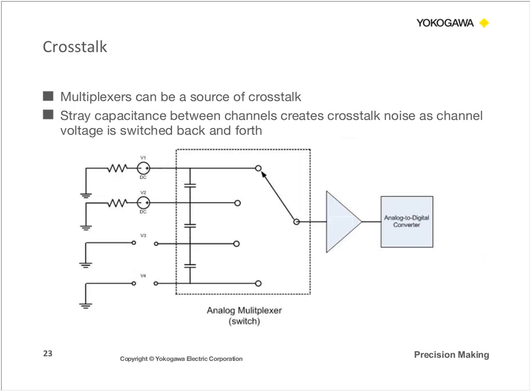So crosstalk is another issue that can occur because you have a ground loop. Crosstalk occurs when you have noise from one channel. Let's say you have a multi-channel data acquisition system. You have noise from one channel that carries over to the next channel. So we're defining crosstalk as the interaction between readings on two or more channels. And this is a pretty common occurrence for data acquisition systems today that implement multiplexing technology, where channels are switching from one to the next, and they're all being controlled by the same analog to digital converter.